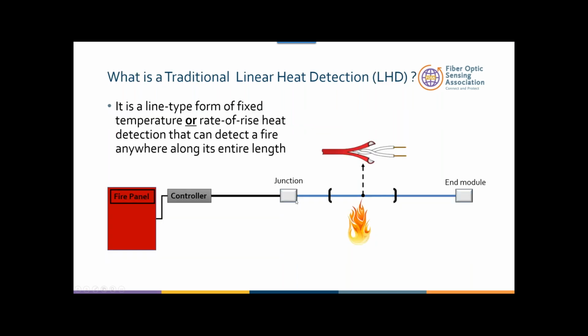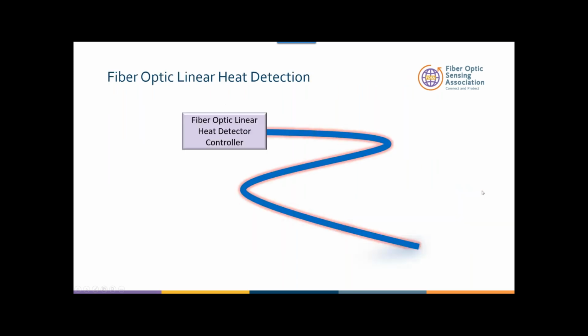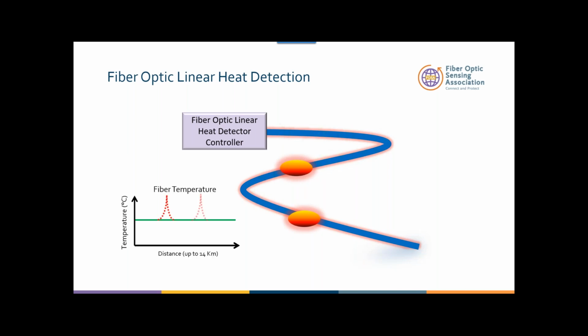The problem is, I won't say the problem is, but at the end of the day, what you get is you have a junction box and you have an end module. The end module is a resistor. That resistor, if the temperature goes up, the resistor is changing the current, and then you get an alarm. The zones have to be set based on the junction box where you do the connection and the end module. In the case of fiber optic linear heat detector, you actually have a laser that gets pulsed. If you get two heat locations, for instance, in this slide, you get a first temperature measurement and you get a second temperature measurement, and that gives you the flexibility and the ability to pinpoint within a meter where the event is occurring.